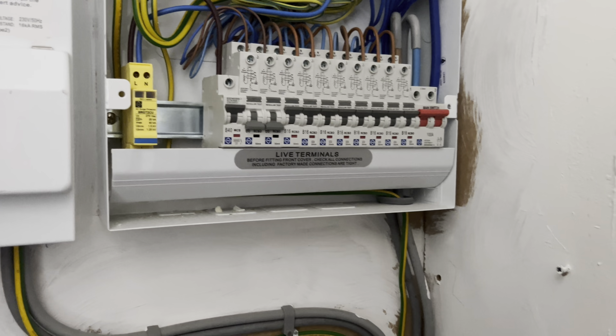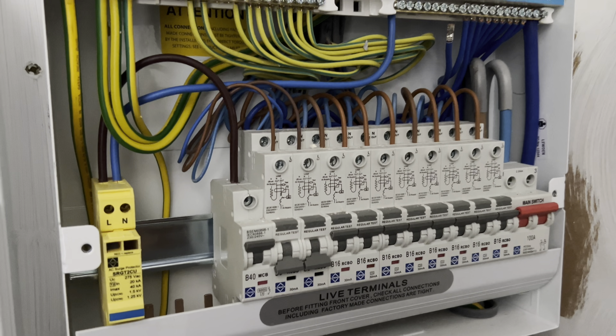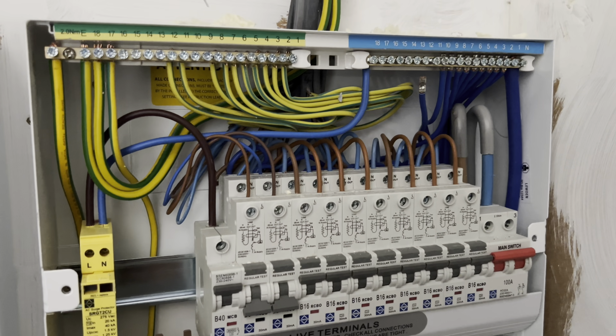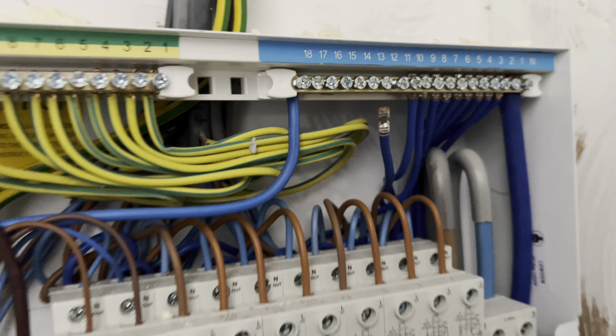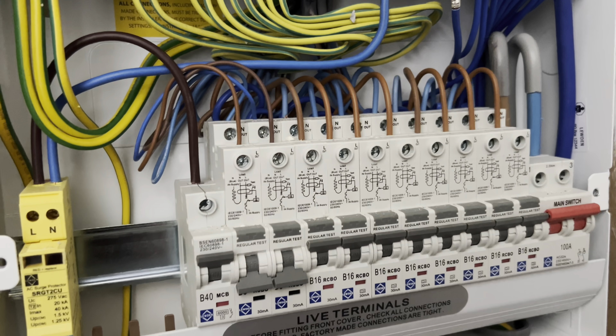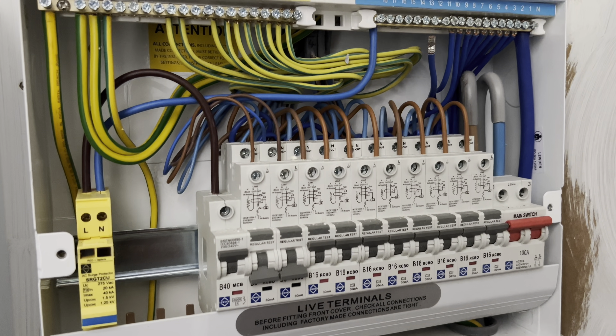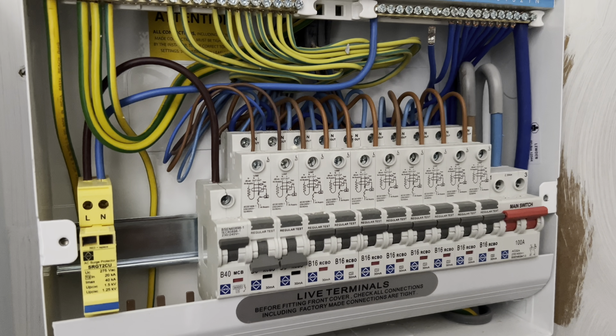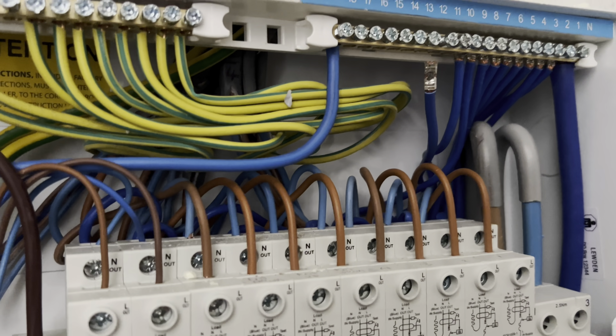Something's really adrift here. So I got my meter to take a look at the voltages and see if I'm getting any voltage on this cable — to see exactly what might be leaking from somewhere. It might be the case I have to do an insulation resistance test to make sure we haven't got any insulation issues between the earth, live, and neutral.